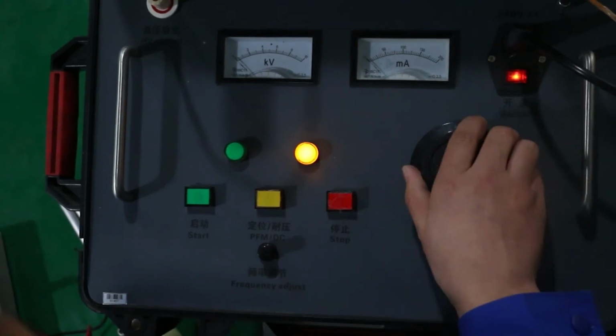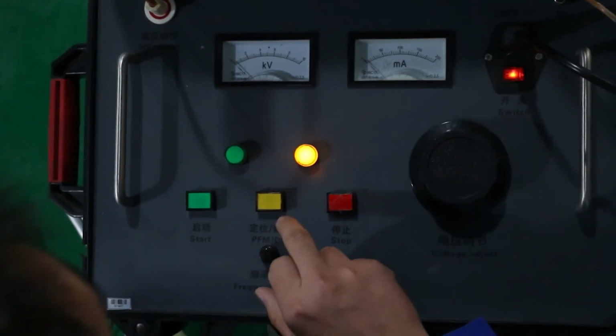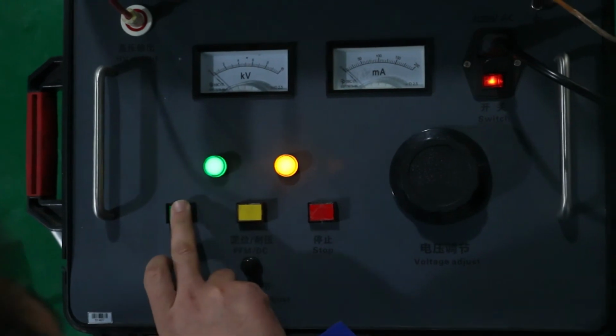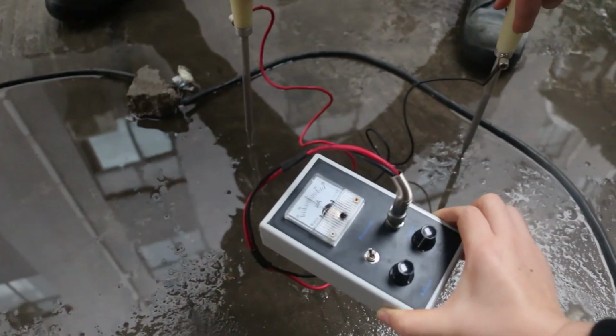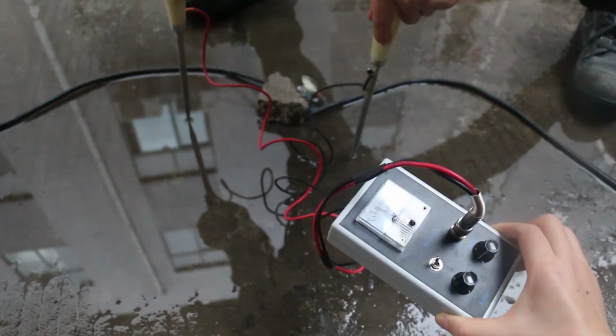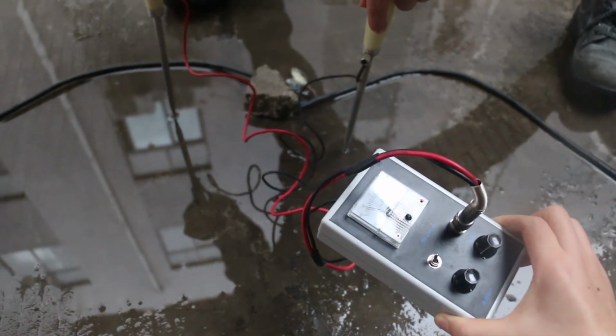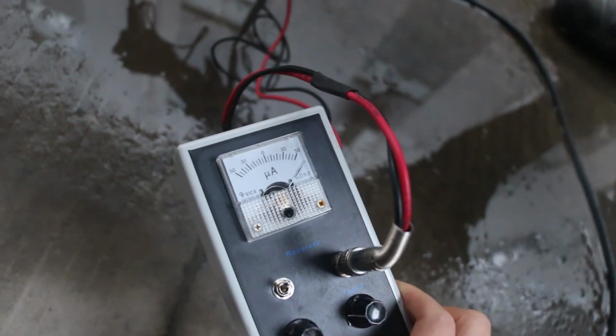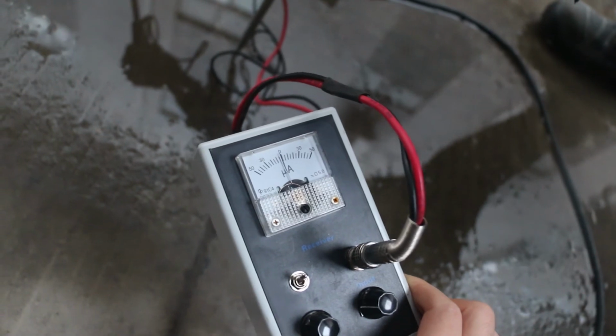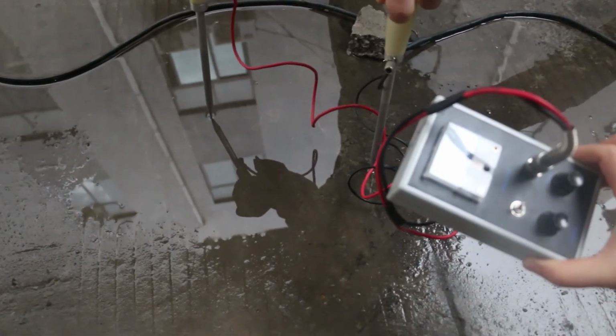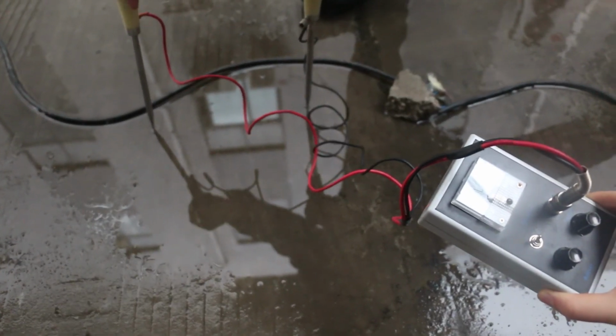Now you can use the receiver box and the ground drill to fix the point within the fault range measured during the rough test. Insert the ground drill into the ground and observe the current indicator on the receiving box. If the pointer is to the left, move the ground drill to the right, and if the pointer is to the right, move the ground drill to the left. Finally, the fault point is found.